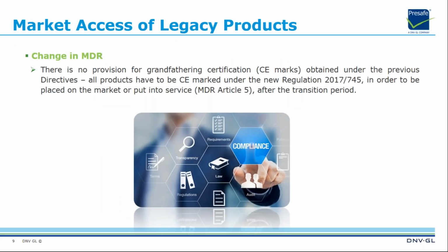The next item, which is a new change, is market access of legacy products. There is no provision for grandfathering certification or CE marks obtained under the previous directives. All products have to be CE marked under the new requirements and the new regulation, MDR, in order to be placed on the market or put into service after the transition period.